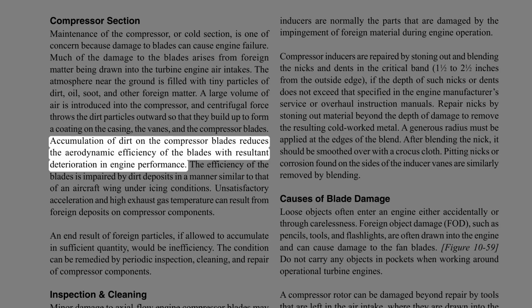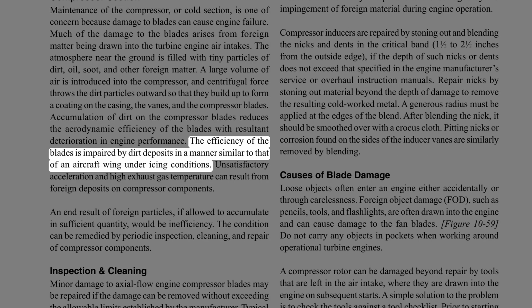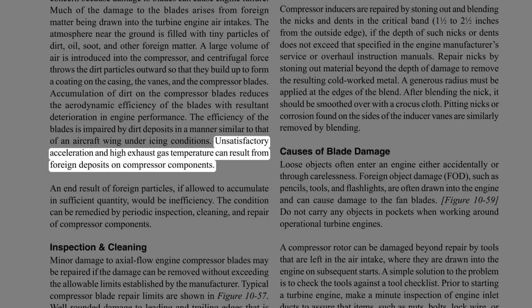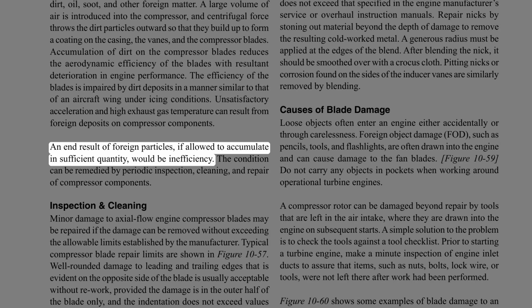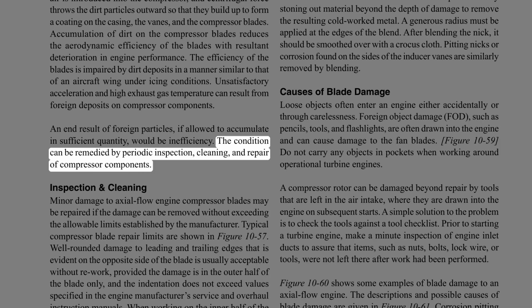Accumulation of dirt on the compressor blades reduces the aerodynamic efficiency of the blades with resultant deterioration in engine performance. The efficiency of the blades is impaired by dirt deposits in a manner similar to that of an aircraft wing under icing conditions. Unsatisfactory acceleration and high exhaust gas temperature can result from foreign deposits on compressor components. An end result of foreign particles, if allowed to accumulate in sufficient quantity, would be inefficiency. The condition can be remedied by periodic inspection, cleaning, and repair of compressor components.